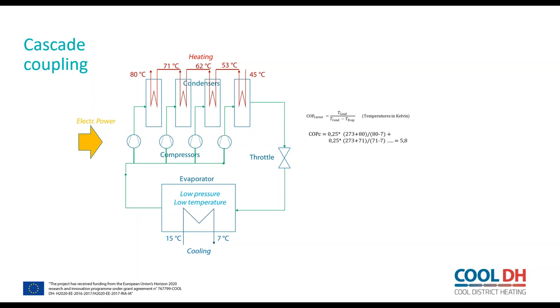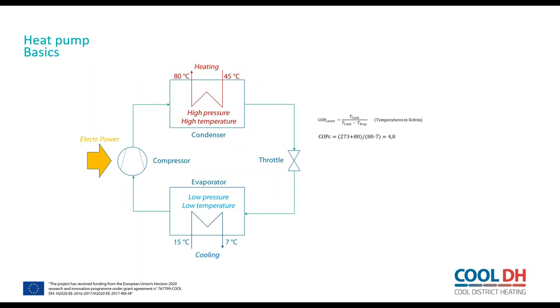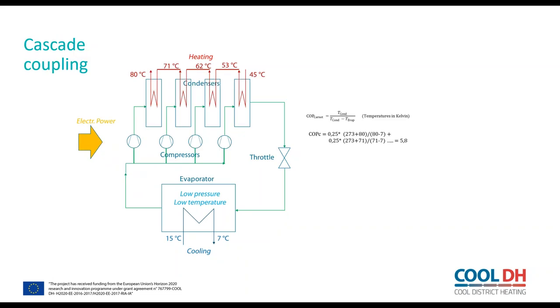I don't know if we can go back, because we can see the theoretical case here, we get the COP of 4.8. In this case, heating from 45 to 80 degrees, meaning a conventional district heating system. And in this case, using the same temperatures on the hot side, otherwise they'll split up in 4, we get a raise by 1 unit to 5.8 in the coefficient of performance. So this is a good thing in theory.